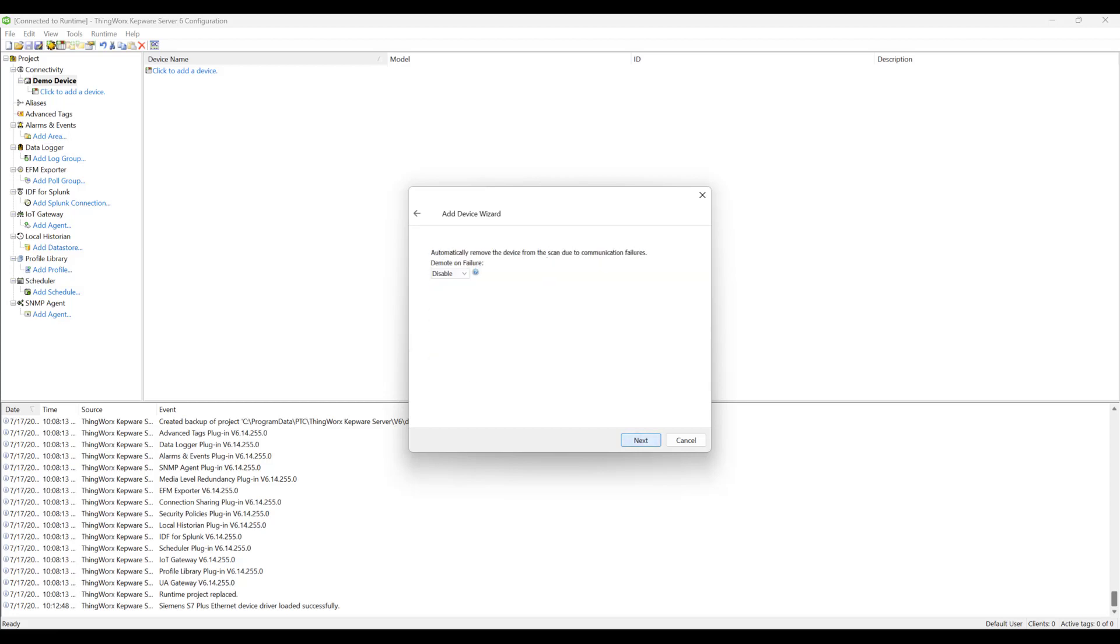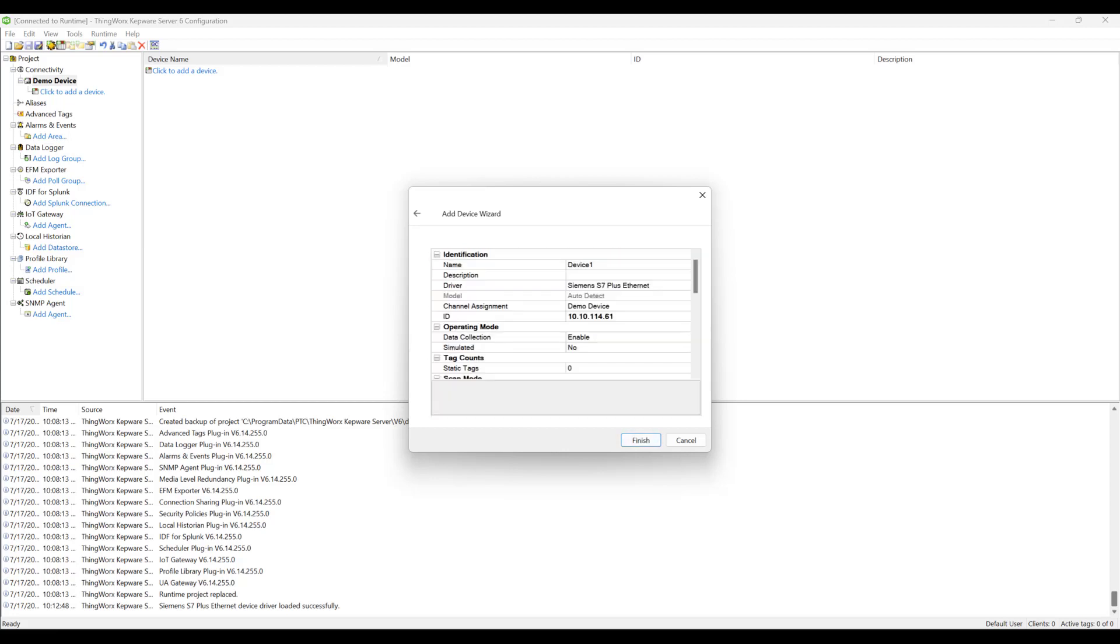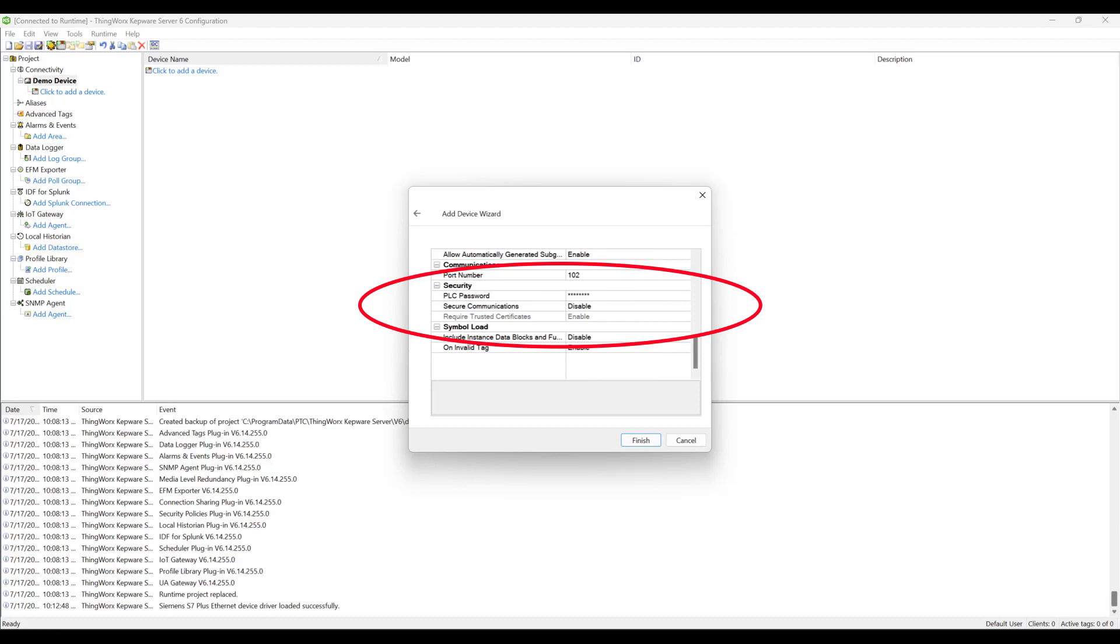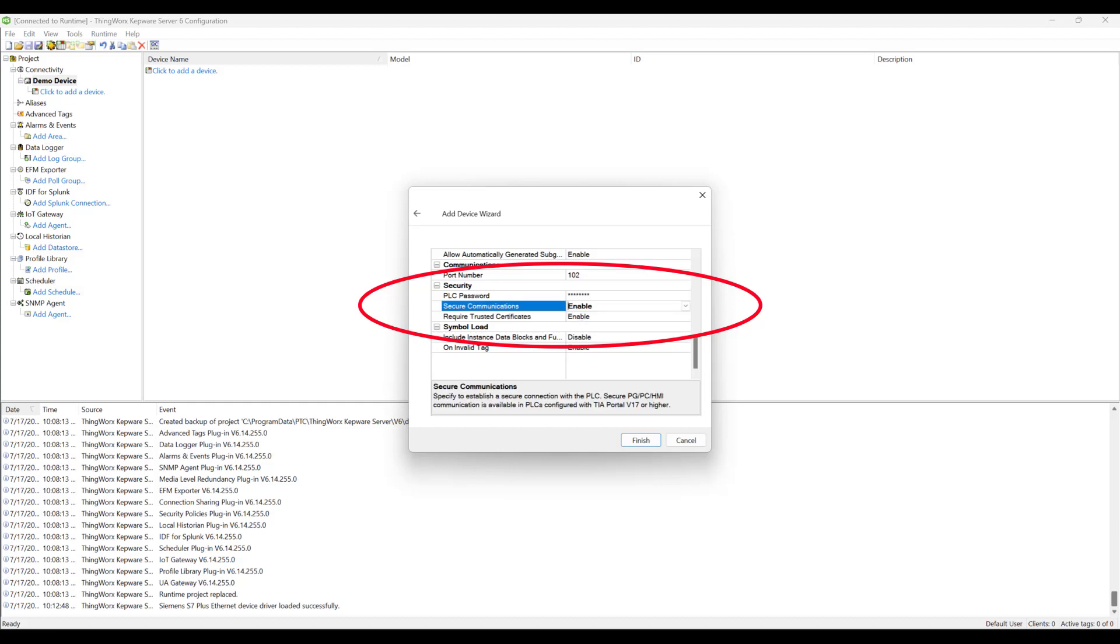...scroll down until you see the security section. Here is where you will enter the PLC password if applicable. Additionally, we can enable or disable secure communications from KepWare down to the Siemens device. When enabled, all information is encrypted. We can also require a trust certificate for the communications. This is only available when the secure communication option is enabled.